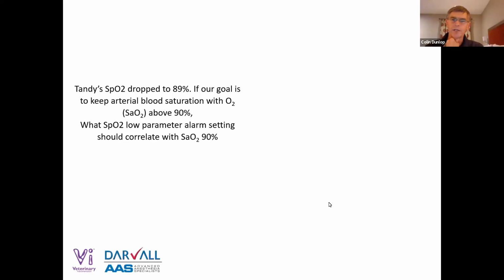We put these things on a lot of anesthetized animals and get readings of between, I would say in dogs, 93 and 97, cats, 91 to 95, when the actual saturation of that animal is 100%. So the pulse oximeter underreads the real saturation by 2 to 3%. So if you wanted to know where the 90% SaO2 point is, it's going to correspond to about 87% in a dog. A cat might be a little bit lower because pulse oximeter readings tend to underestimate in cats a little bit more because there's less tissue and less flow. So I normally set my pulse oximeter low alarm level at 87%, which corresponds to an arterial saturation of 90%. I hope that explains the answer.